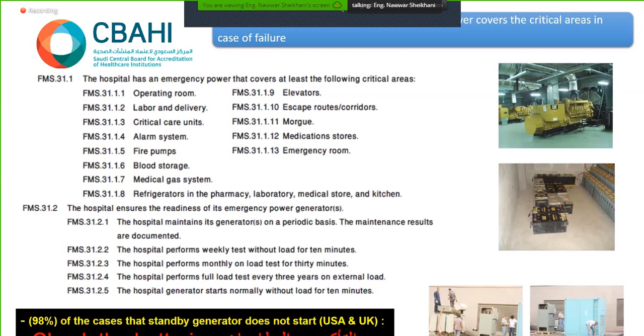Please make sure of the batteries, because there are statistical studies done in the USA and UK that 98% of the cases where a standby generator doesn't start were because of the batteries, even if the generator is new. Please check the batteries. Check that the terminals are clean, and if possible, you can cover them, especially in case of dust storm.